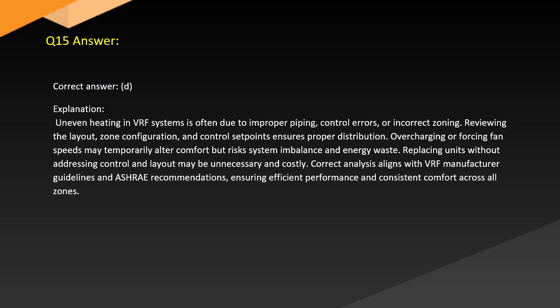Answer. Correct answer, D. Explanation. Uneven heating in VRF systems is often due to improper piping, control errors, or incorrect zoning. Reviewing the layout, zone configuration, and control set points ensures proper distribution. Overcharging or forcing fan speeds may temporarily alter comfort but risk system imbalance and energy waste. Replacing units without addressing control and layout may be unnecessary and costly. Correct analysis aligns with VRF manufacturer guidelines and ASHRAE recommendations, ensuring efficient performance and consistent comfort across all zones.